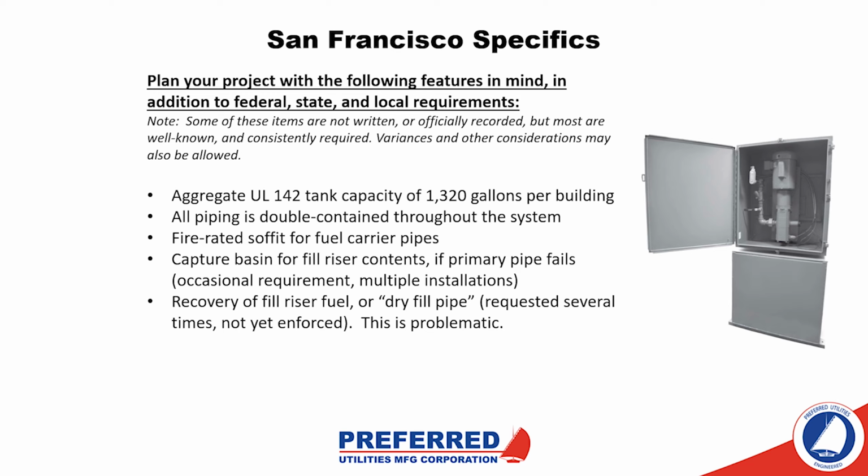Next item, fire rated soffit for fuel carrier pipes. Same thing here, essentially required on basically every project. We tend to see 2-hour rated soffit requirements. I have heard people talk about 3, but I don't think I've encountered any of those personally.